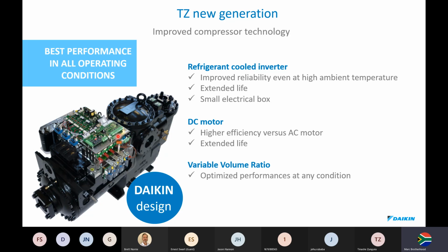So even in the event of load shedding and this chiller suddenly stops, conventional electronics would rely on a little cooling fan within the cabinet. That would stop, so these electronics would overheat, and the heat conducting paste on the back would harden with time, and you would blow your IGBT module and you blow this whole inverter board.